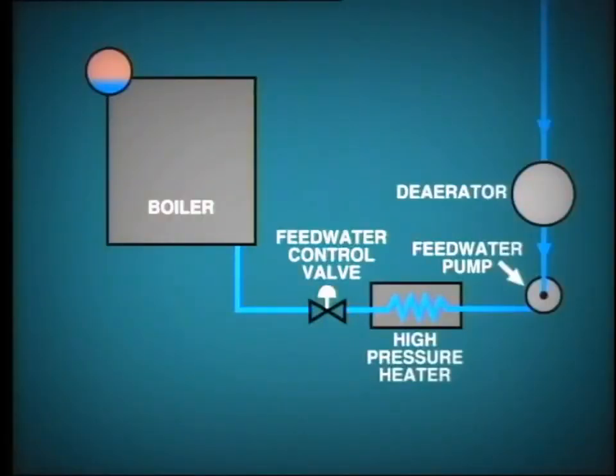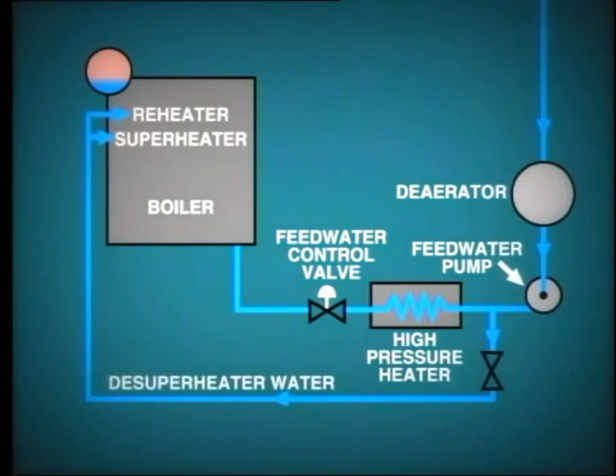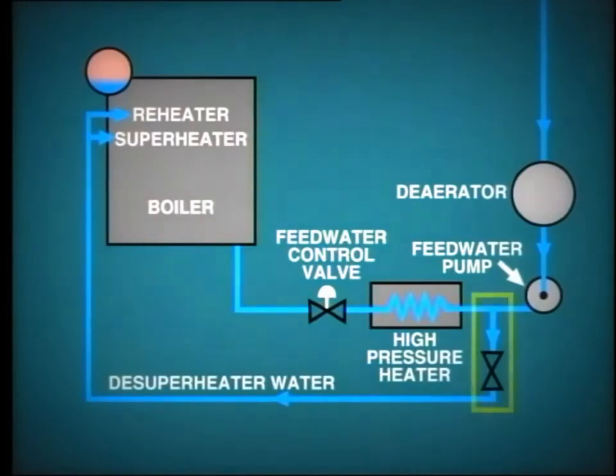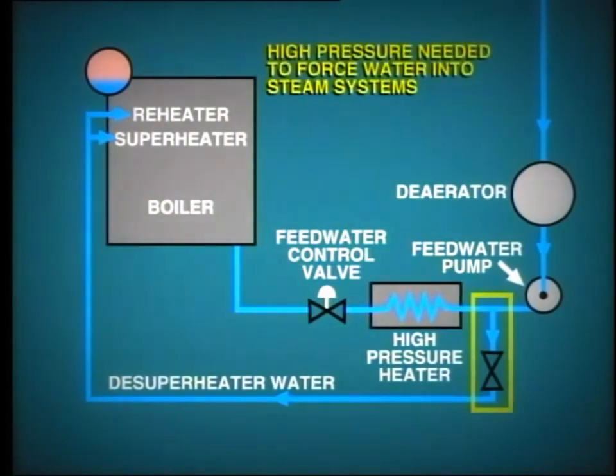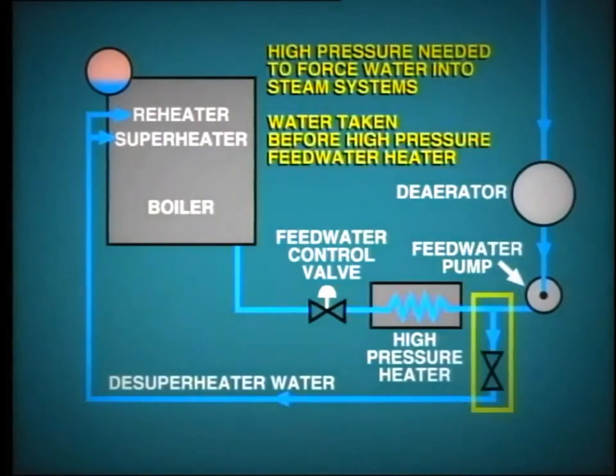As well as providing feedwater for the boiler, the feedwater system provides water for the desuperheaters on the main steam and reheat systems. Desuperheating water is tapped off the feedwater system at a point fairly close to the feedwater pump. A sufficiently high pressure must be available in order to force the desuperheating water into the steam systems. The temperature of the water should be such as to provide cooling action; therefore, it should be taken before feedwater passes through the high pressure feedwater heater.